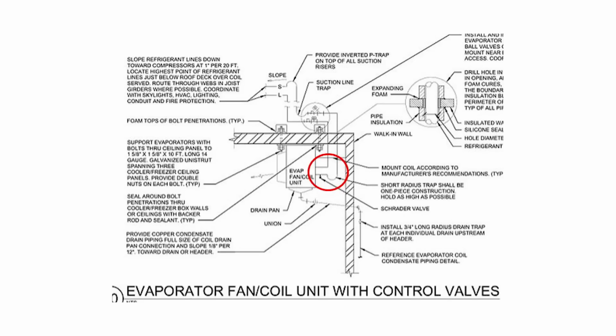Sure, you're right. So, once again, talking about the suction. We're coming out of the evaporator on our suction pipe. This is assuming the pipe that's leaving my evaporator has got to go up at some point. If it's dropping down, no big deal. I don't need a trap there. But if that pipe is going up, and it almost always does, I need a trap immediately coming out of the evaporator at the bottom of that, we call the riser, the pipe that goes up. In fact, anytime I have a pipe that goes up more than the diameter of the refrigerant pipe, we call that a riser.